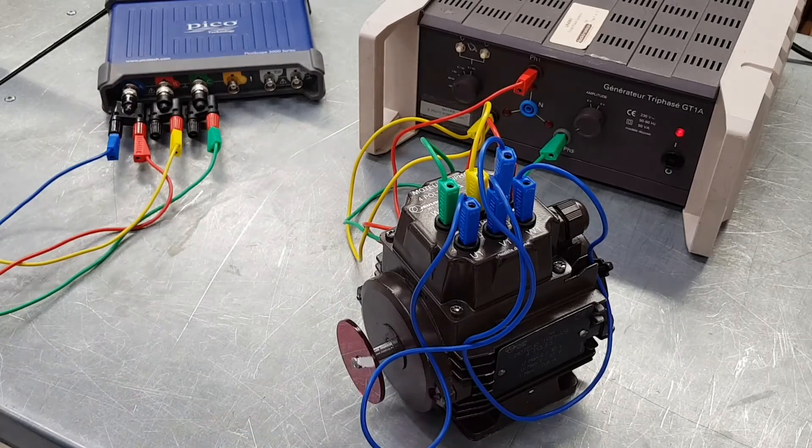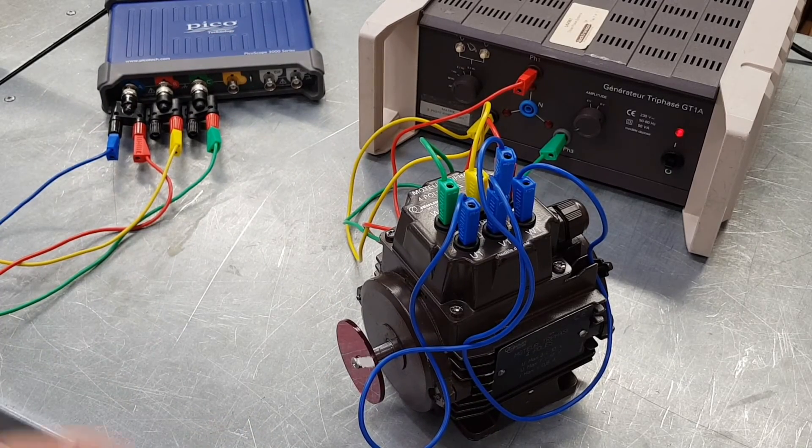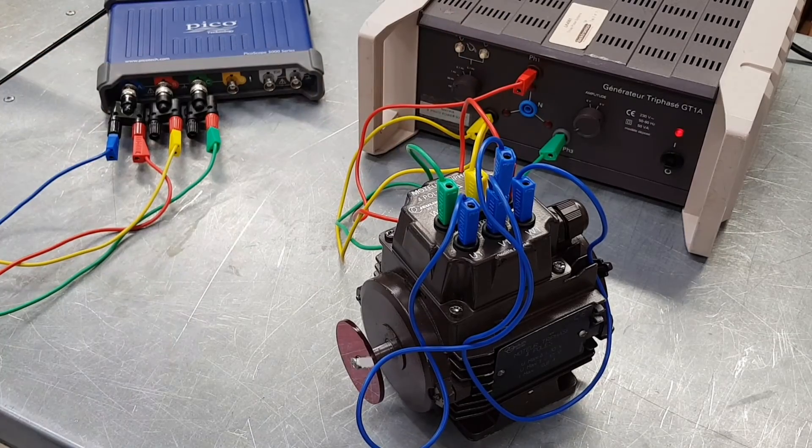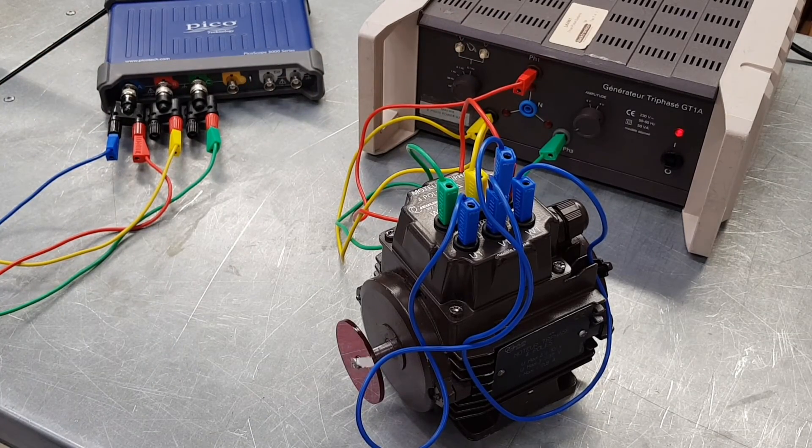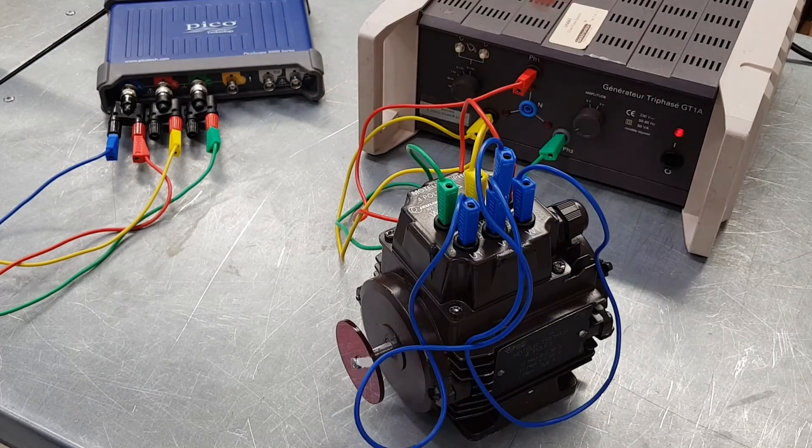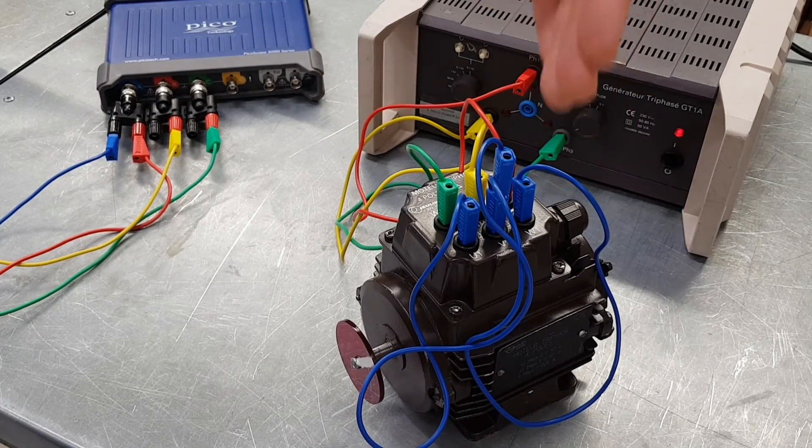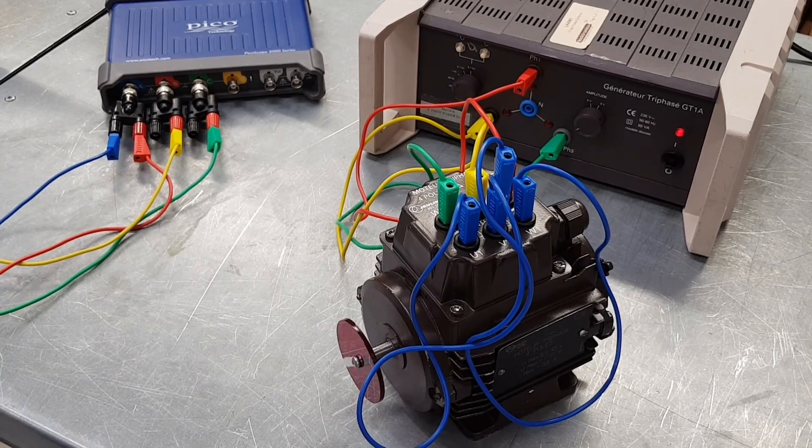Each of the coils inside this motor are exactly the same, which means there is the same amount of current coming in through each one of these supplies. That means we've got a balanced load, so there is absolutely no neutral requirement because there is no current flowing back through the neutral of this circuit.